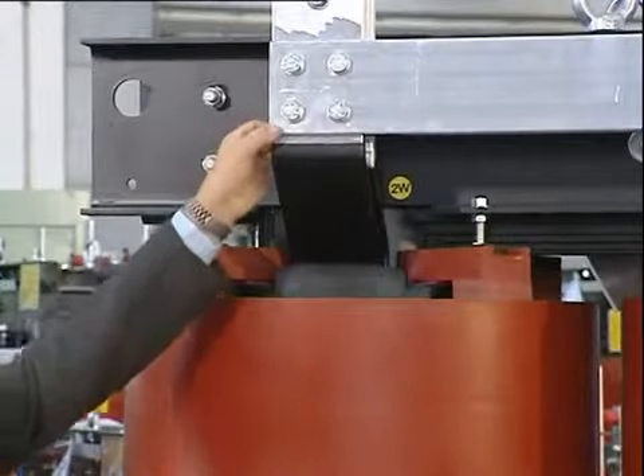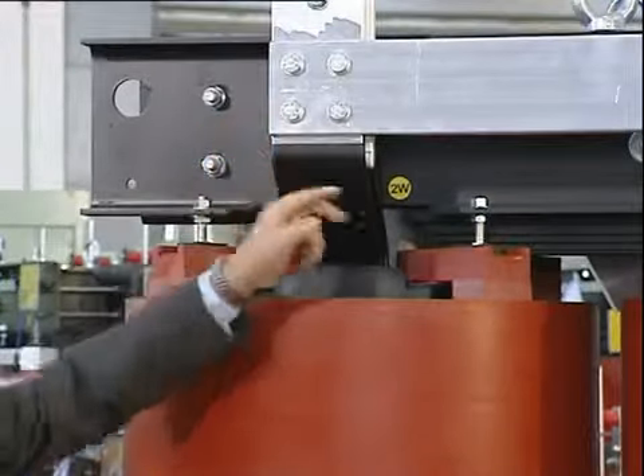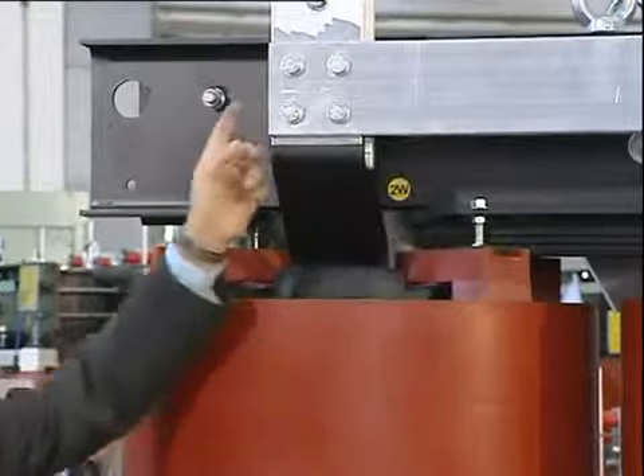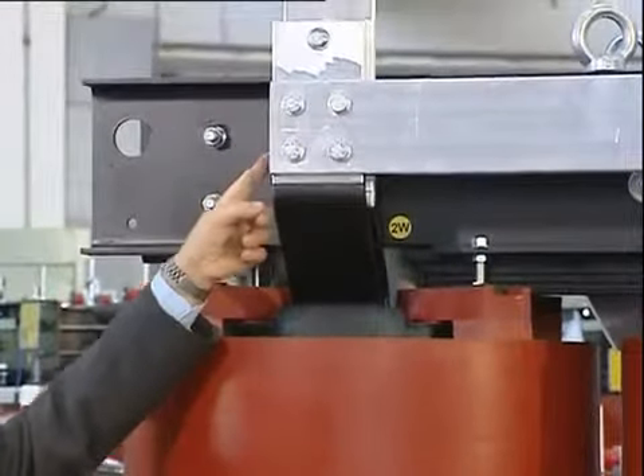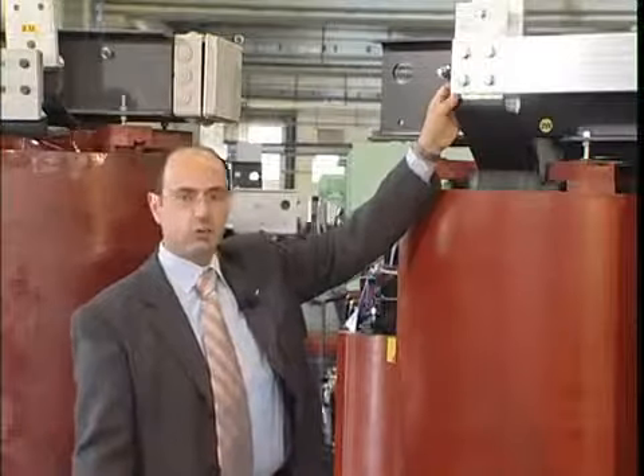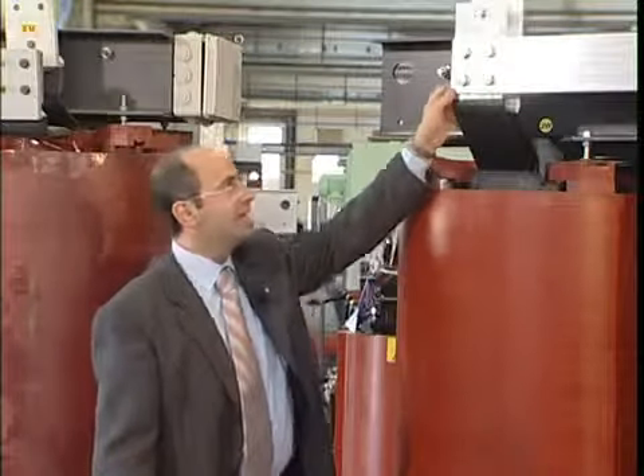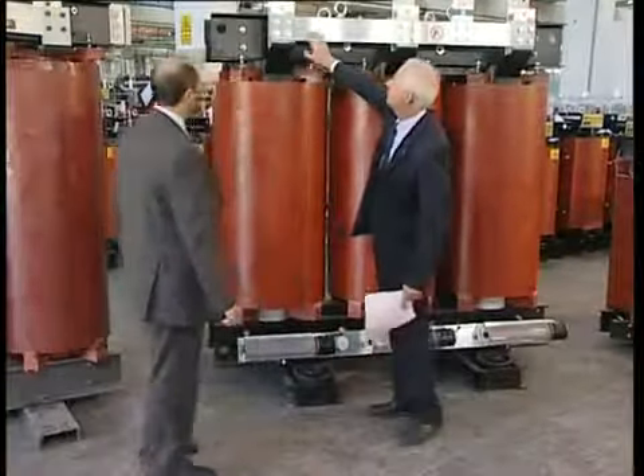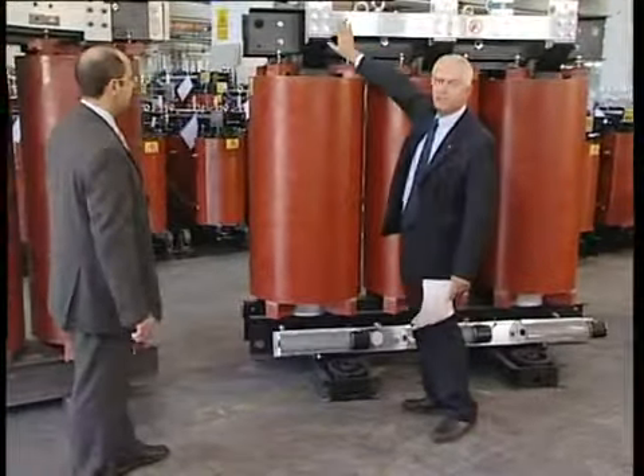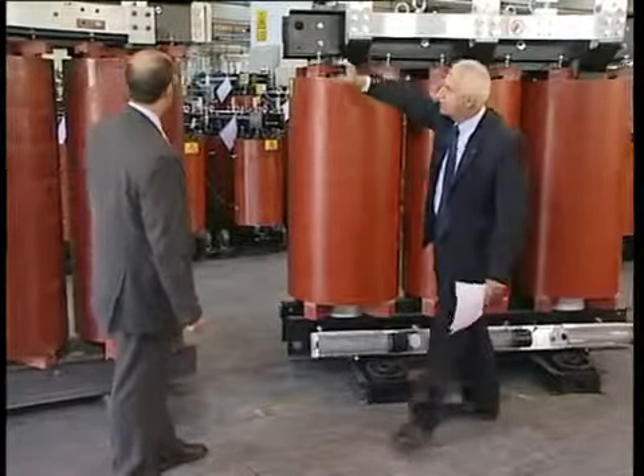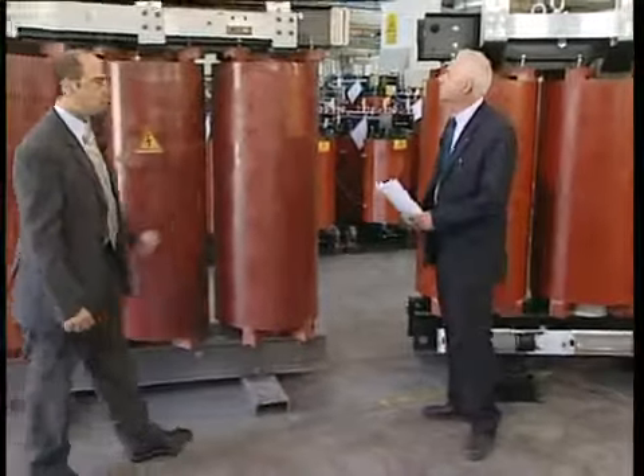and comes out connecting to the star connection made with a double bar, i.e. with a double contact surface, in order to minimize any additional resistance in the electrical contact. Here we can indeed notice a largely homogeneous distribution without any weak points. Let us move on to the other one.